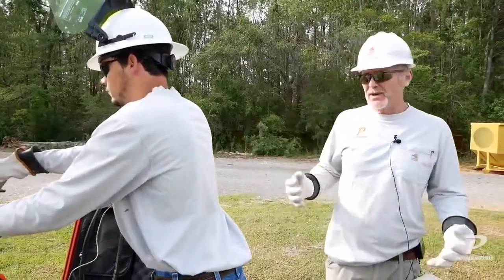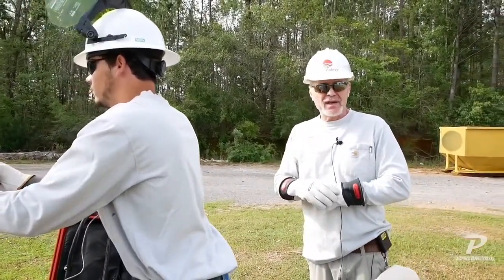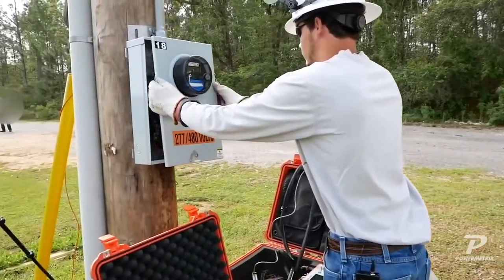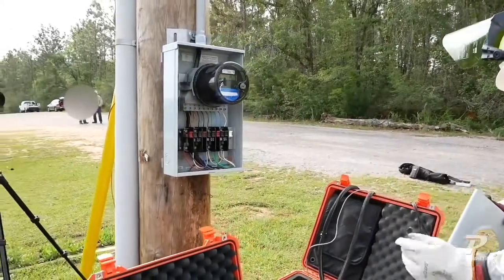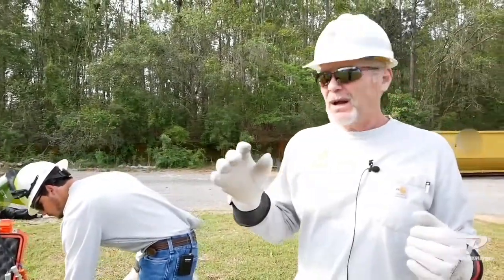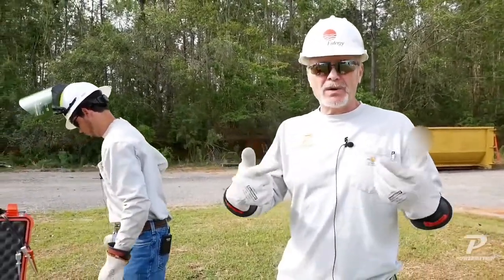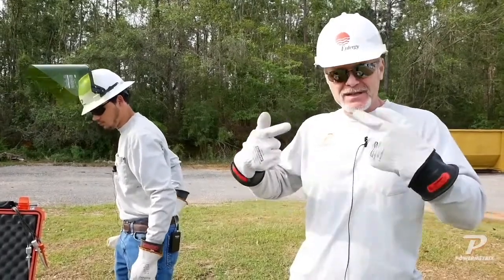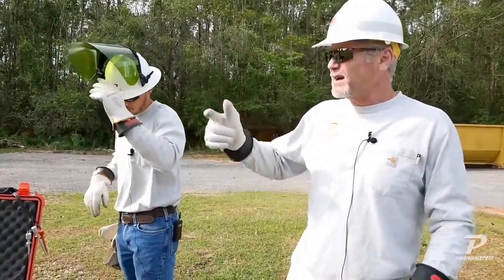So it is typically on these transformer rated meters, you have 1.8 as your K sub T, which we may as well say this, we haven't said it yet, but what that means is for every 1.8 watt-hours, you get a pulse. Okay, so that's what's happening. It is giving you a pulse over every 1.8 watt-hours. So that's what we're looking for.